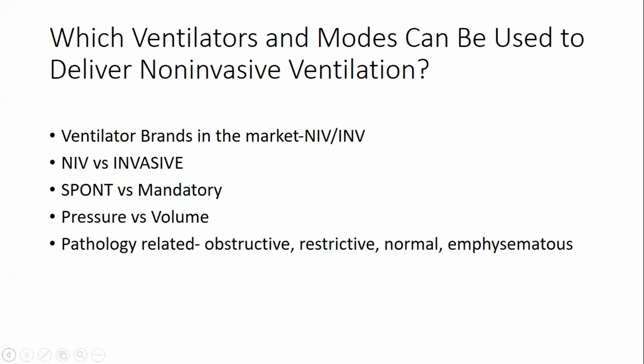Always change the modality to NIV if you are using NIV. There are situations where patients have been erroneously put on NIV, but they are actually on an invasive mode on the ventilator. Some ventilator brands may also not do invasive and are only able to do NIV, but the majority are able to do both.